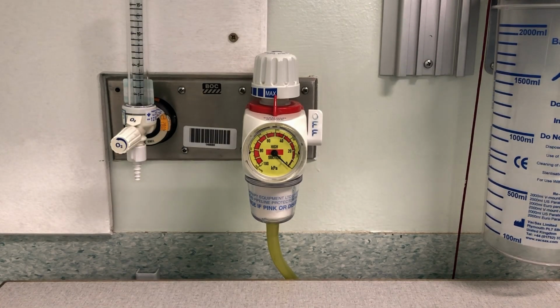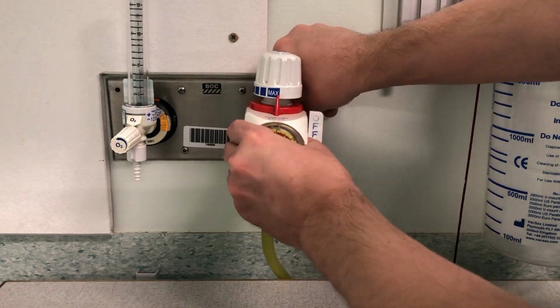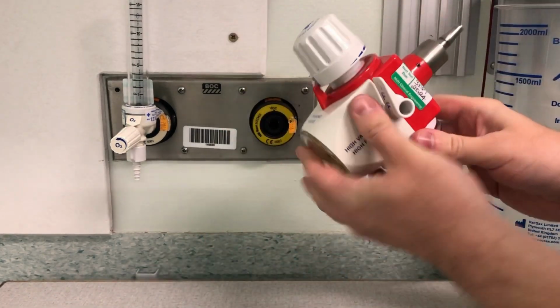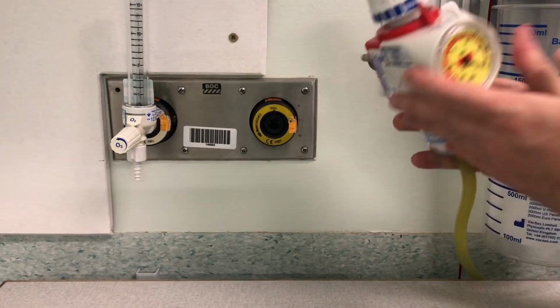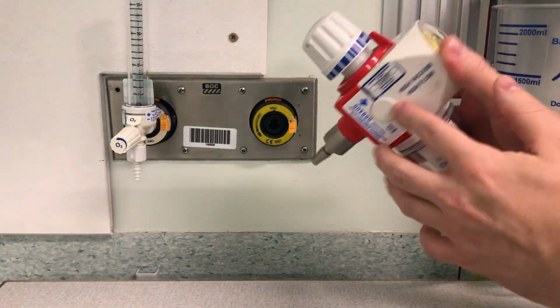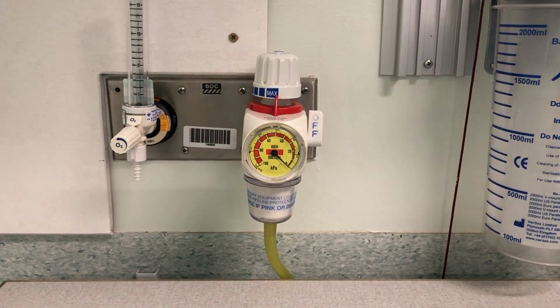To check for damage, wear, faults and service date, check for obvious signs of physical damage to the controller, and then check the service sticker to ensure that the negative vacuum suction controller is within its service period. Within the trust, there are multiple types of negative suction controller available. There are high vacuum controllers, which are red, and they measure between 60 and 80 kPa. There are low vacuum controllers, which are orange, and that's between 0 and 20 kPa. There's a thoracic vacuum controller, which is green, and that measures between 0 and 4 kPa.